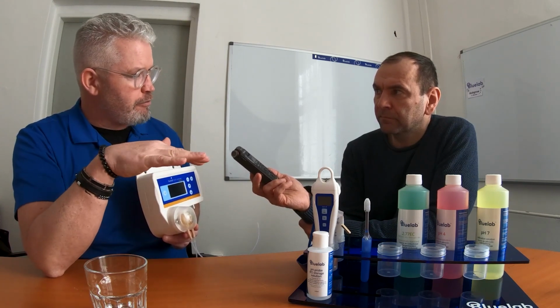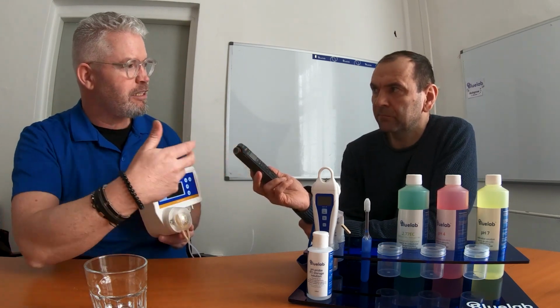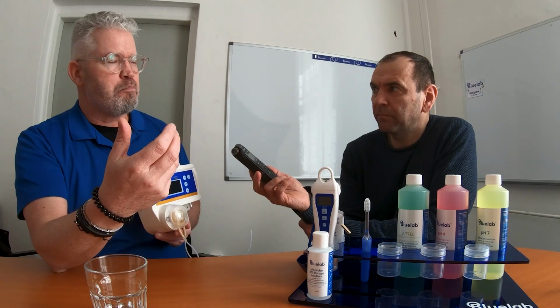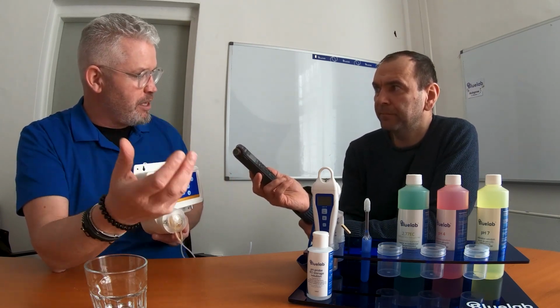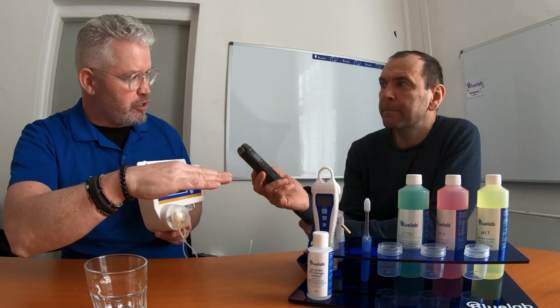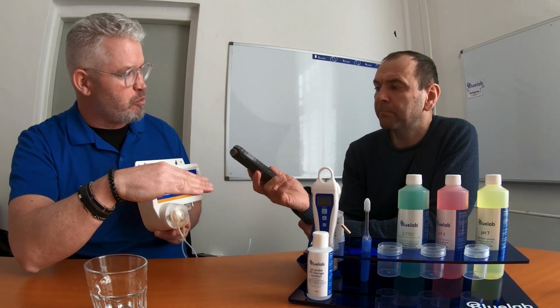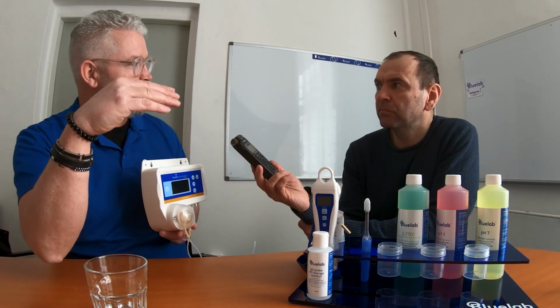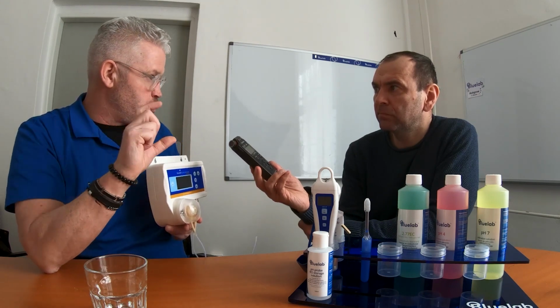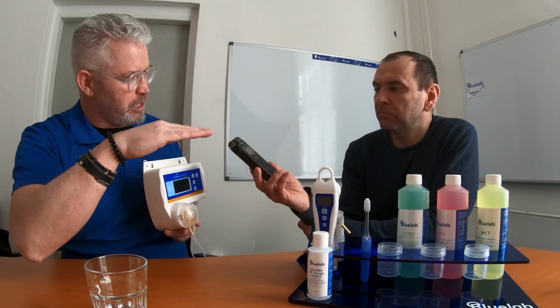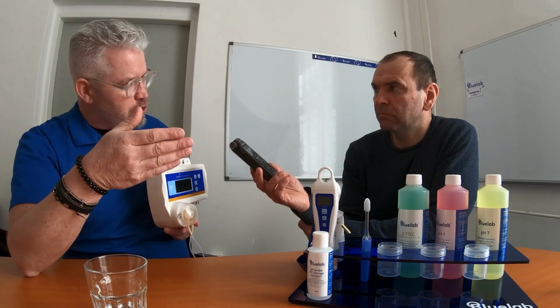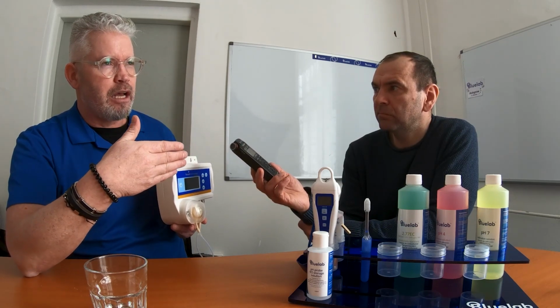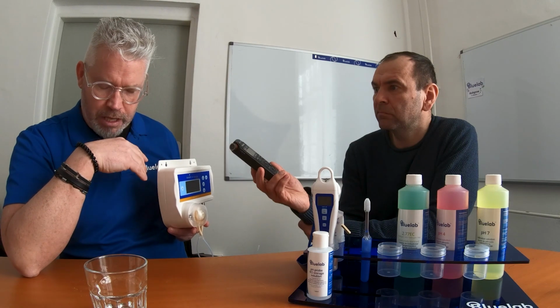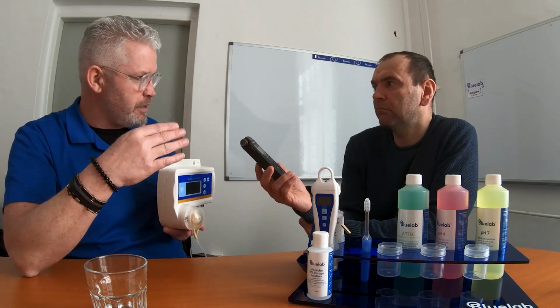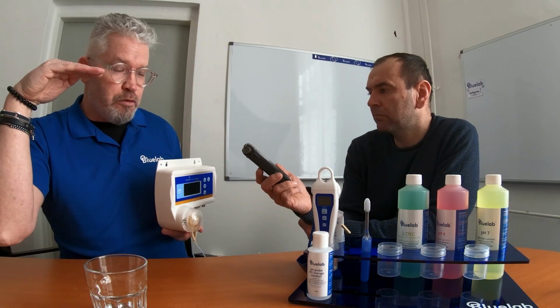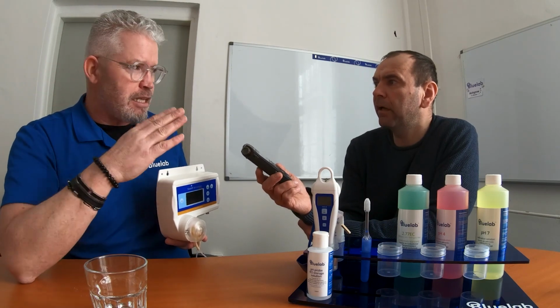We also have an off time. Sometimes you need to mix the water with the acid, and then it stabilizes. It measures again, and when the set point isn't reached yet, it doses again for a short amount of seconds. So it's really a reliable, slow kind of instrument to prevent stress to your plant - that's actually what it does.